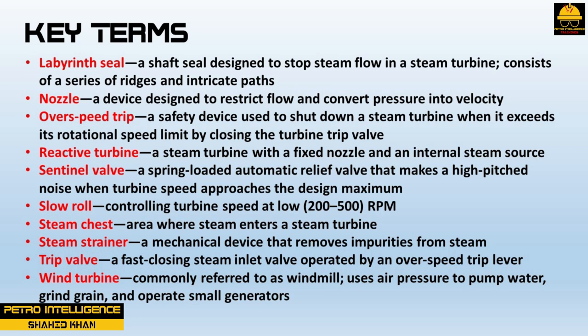Overspeed trip is a safety device used to shut down a steam turbine when it exceeds its rotational speed limit by closing the turbine trip valve. Reactive turbine is a steam turbine with a fixed nozzle and an internal steam source. Sentinel valve is a spring-loaded automatic relief valve that makes a high-pitched noise when turbine speed approaches the design maximum. Slow roll is controlling turbine speed at low 200 to 500 RPM. Steam chest is the area where steam enters a steam turbine. Steam strainer is a mechanical device that removes impurities from steam. Trip valve is a fast-closing steam inlet valve operated by an overspeed trip lever. Wind turbine, commonly referred to as a windmill, uses air pressure to pump water, grind grain, and operate small generators.